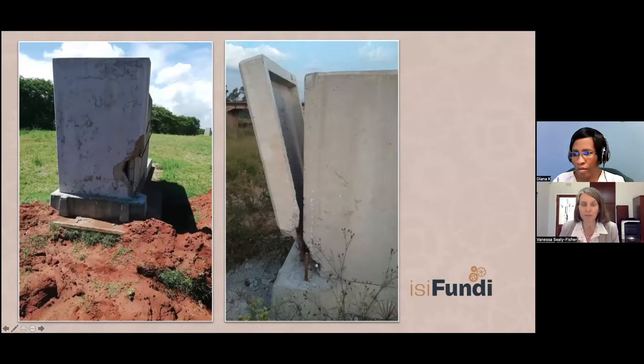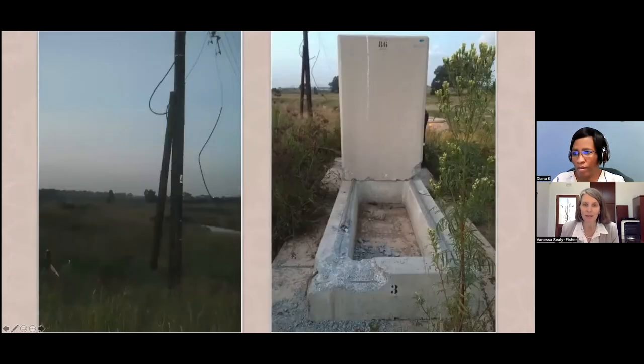Whilst the damage was severe — probably hundreds of thousands of rands — the net value of what was stolen is almost insignificant. Rectifiers were then housed in more secure concrete bunker-style enclosures, and even these were subject to vandalism. Here we can see one was completely destroyed, the front completely taken off, and in the background you can see they've also taken the external power supply from the pole — not helpful for keeping power to the cathodic protection system.